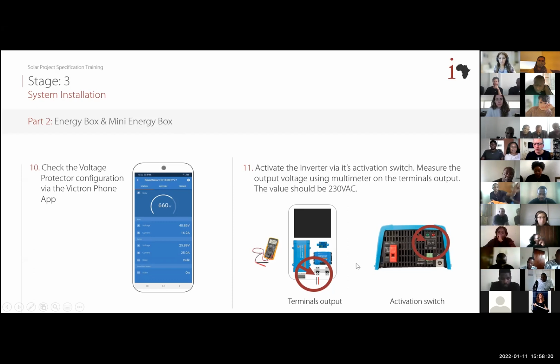After checking the charger, battery, and voltage protector, the next thing is to check that the output voltage level at the terminals of the inverter is okay. You use a multimeter on the two terminal outputs and you should measure 230 volts AC. Also, if the inverter is operating accurately, you should see a green light here - if the light is red or there's no light at all, it means the inverter has an issue. Another thing to consider: the inverter's on/off switch - sometimes you'll find it off, meaning at the center level. If it's off, activate it and then measure the voltage on the output terminals.